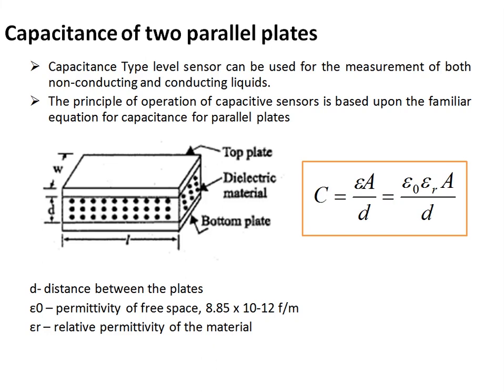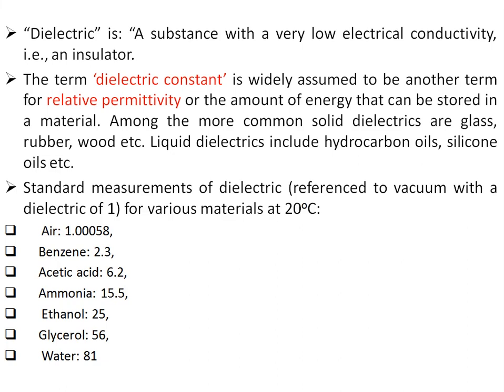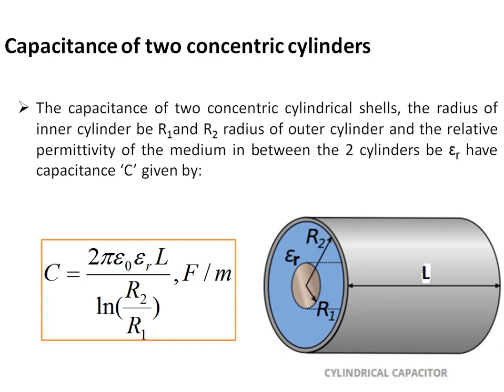For non-conducting liquids, the varying parameter is the dielectric constant; for conducting liquids, it is mainly the distance between the plates. A dielectric material is a substance with very low electrical conductivity — essentially an insulator. Common solid dielectrics include glass, rubber, and wood; liquid dielectrics include hydrocarbon oils and silicone oils. The dielectric constant of various materials at 20°C includes: air (~1.0), benzene (2.31), glycerol (56), and water (81).